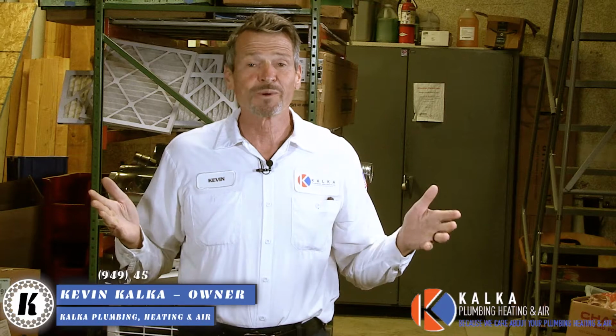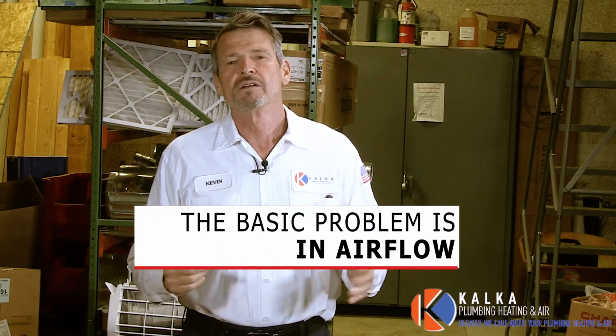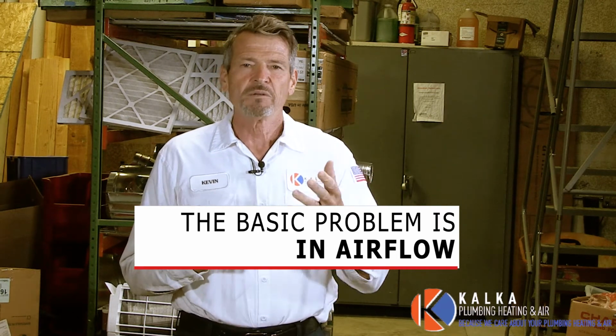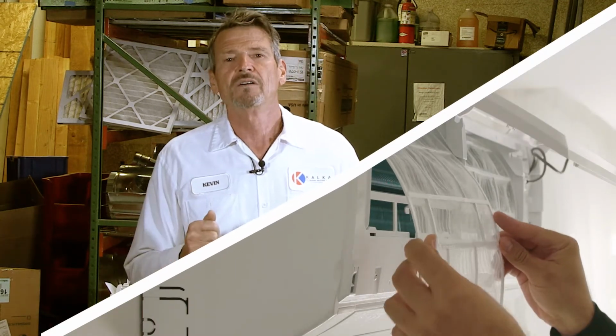So you're looking at Frosty the Snowman here and you're wondering what's causing this. Well, typically it's airflow. Airflow gets restricted somehow and it will cause that system to ice over every time. So that's the thing that I'm gonna look for first, is the airflow. Maybe you can look yourself, check your filter, had it been replaced.